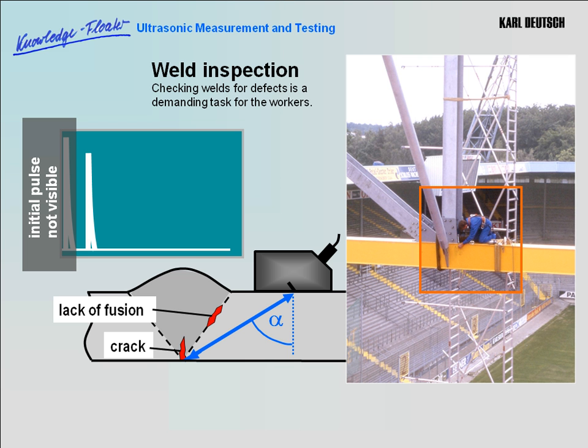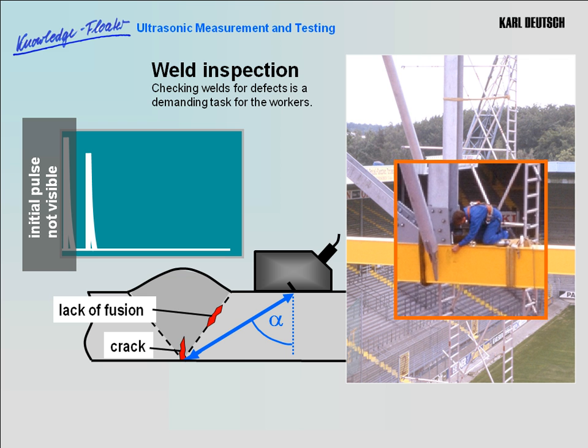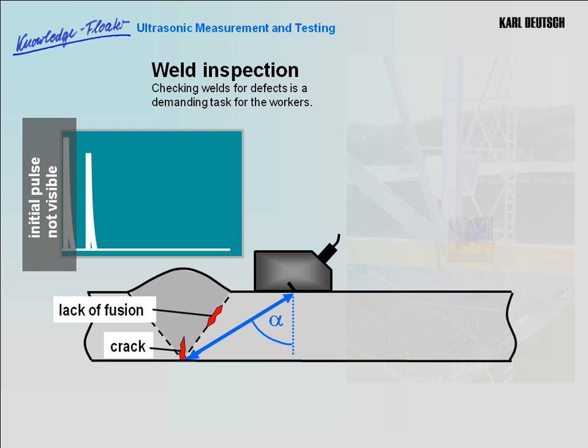Weld inspection. Checking welds for defects is a demanding task, the high school of ultrasonic testing. Angle beam sensors are used to transmit sound waves obliquely into the material. Depending on the particular weld, thickness, distances involved, reflective conditions, etc., various types of defects can be detected at the bottom of the weld, for instance cracks or non-welded root.